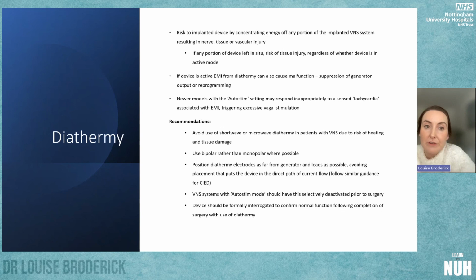With respect to the activation of the device, if the device is active, EMI from diathermy can also cause malfunction, either by suppressing generator output or reprogramming some of the parameters. And as I mentioned, the newer models that have the auto-stim setting activated may equally respond inappropriately to what it senses as a tachycardia associated with electromagnetic interference, and this can trigger excess vagal stimulation, which can have deleterious cardiovascular effects for the patient.